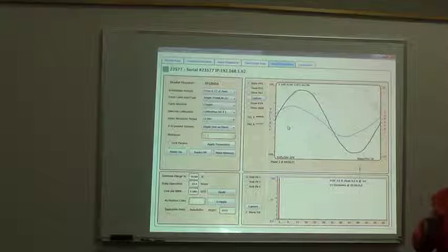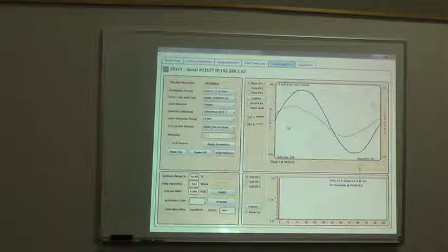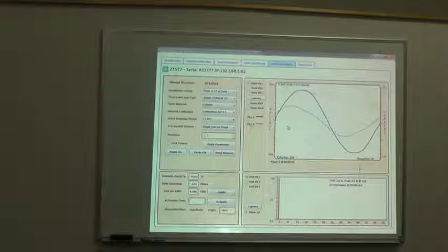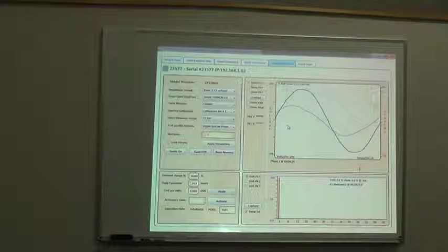So you have to try to understand, that's why you have to do one phase at a time, so there's only one available. You know what I'm saying? When you do an install, you really have to install one phase at a time. That way it reduces your chances of an error by like 90%. Yeah. So we need to make a note of that for installation.